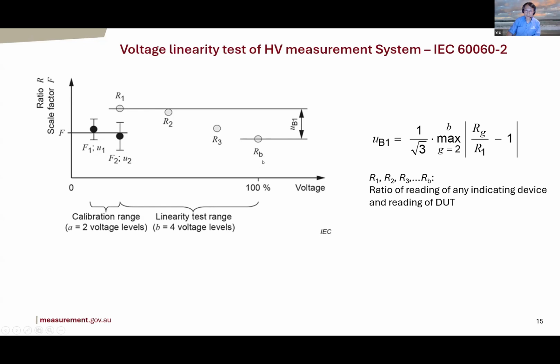Then you do the so-called linearity test. The linearity test is done by comparing the reading of your measurement system to the reading of another reading device, whatever that can be, right? You compare the ratio at the different levels, and then you work out the maximum deviation of the ratio from the ratio at the lowest calibration point. So that deviation becomes an uncertainty contribution to the uncertainty budget of the subsequent use of the measurement system for testing. So this ensures that you have adequate calibration uncertainty.